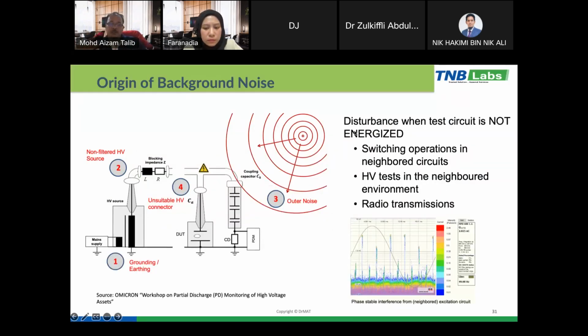Of course, when we do the PD testing, different kinds of noise will be present in our measurements. Disturbance or noise can occur when the circuit is not energized. What does it mean? In the lab, we have noise or disturbance coming from the grounding. So in our test setup, we need to have good grounding. And then sometimes the applied voltage is not clean, and this unclean source will also generate PD. And then the other is outer noise, the environmental noise.